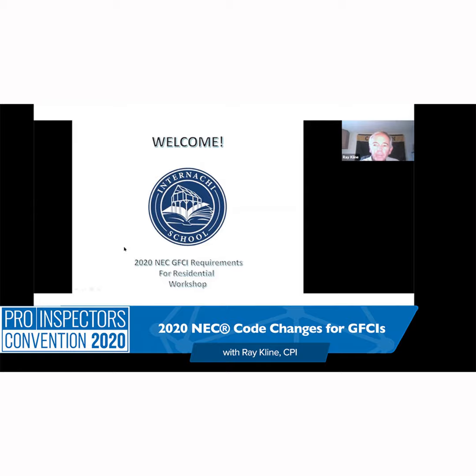Okay. Is there a certain number of receptacles that can be on a given reset receptacle? That was confusing. Typically if I had a GFCI circuit feeding some bathrooms, I probably would have one GFCI feeding 2, maybe 3 bathrooms downstream. If you're feeding a garage, you could probably put 4 to 6 other receptacles on there. I don't think I'd go over 6 on a GFCI.